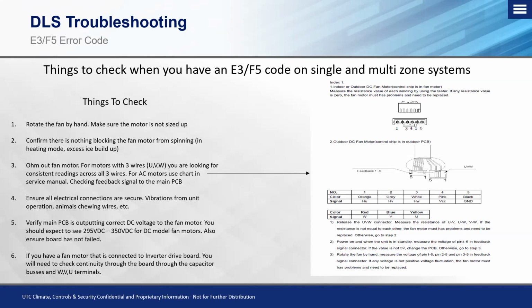Once we've got those simple things out of the way, then we want to start getting into the more advanced side of things with troubleshooting the fan motors. So, of course, it's going to depend on what type of fan motor you have, whether you're dealing with an older AC style motor or the newer DC style motors. So, for motors with 3 wires, U, V, and W, just like we have going to our compressor, you're looking for consistent ohm readings across all 3 wires, just like you would ohm out any normal motor or compressor. You want consistency across them.